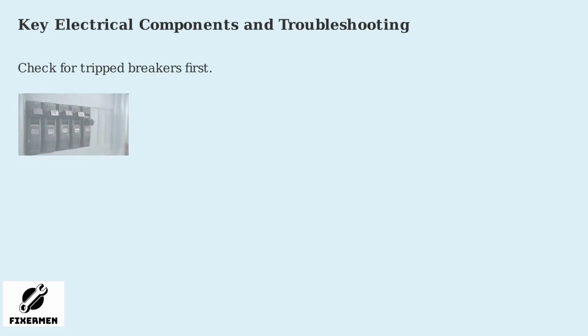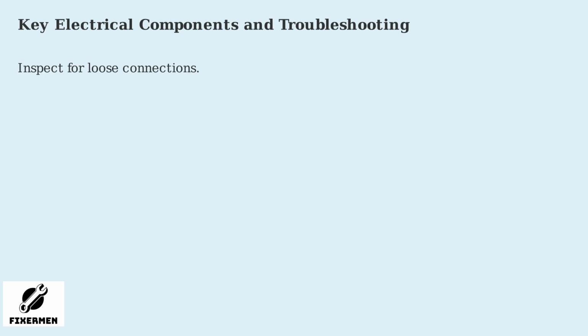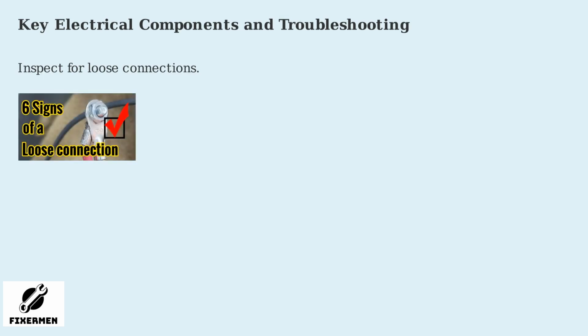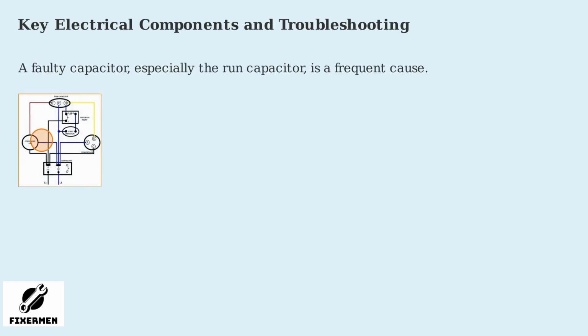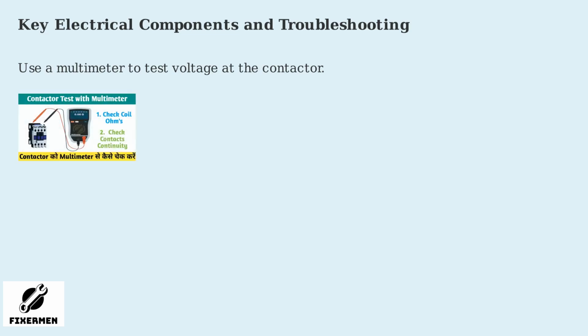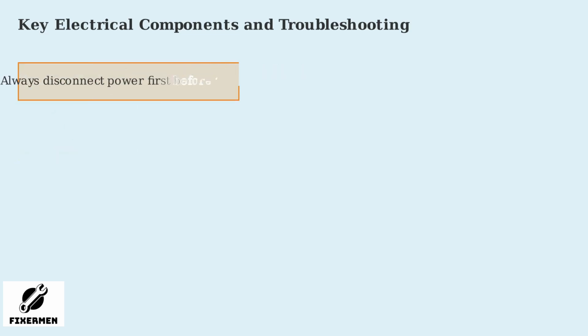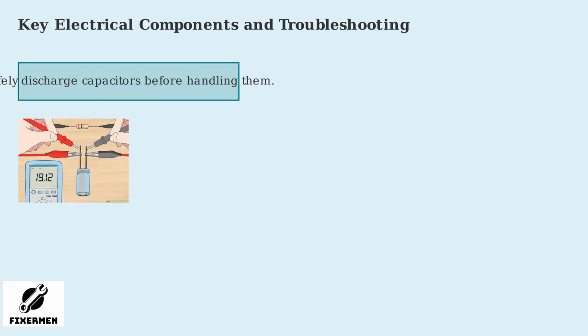Always start by checking for tripped breakers in your electrical panel. Next, inspect all electrical connections for looseness or damage. A faulty capacitor, particularly the run capacitor, is one of the most common causes of startup failure. Use a multimeter to test voltage at the contactor terminals. Important safety warning: always disconnect power from the unit before performing any electrical tests. Remember to safely discharge capacitors before handling them to avoid electrical shock.